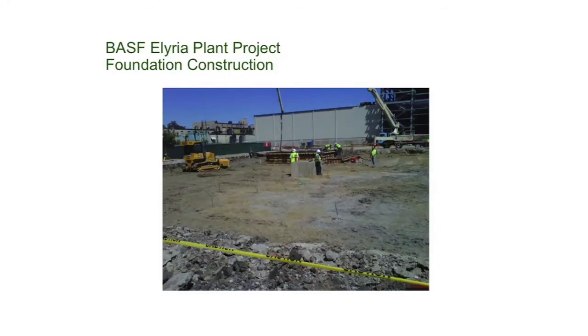And here we've already started the backfill, and we were pouring the foundations for the dead tank breaker, the structural steel framing, the transformer foundation and containment pit. And we had already, if you can see the small rods, we've already had the grounding system installed. But as usual, you dig a hole in the ground, and the next thing that happens is it rains. So that summer was the wettest summer in history for the Cleveland area. Again, but we were able to overcome that, deal with it, and maintain the schedule for the completion of the substation.